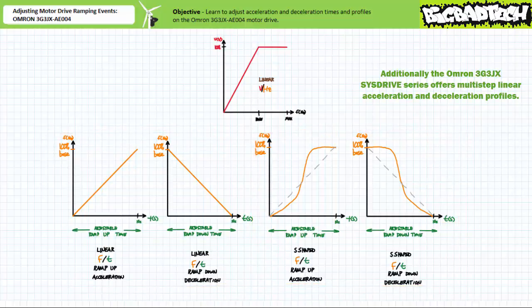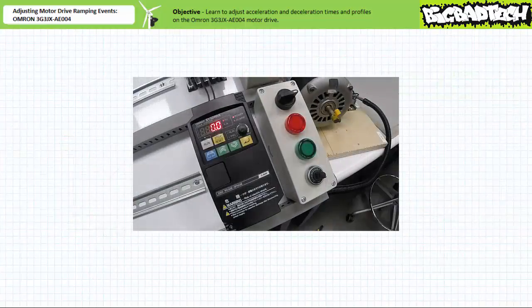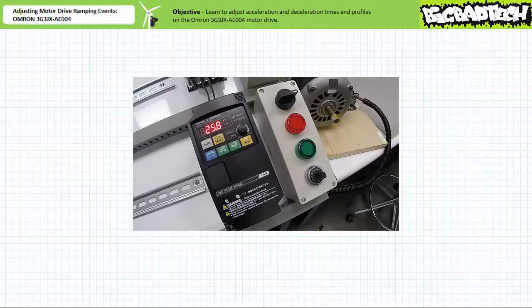The default profile for both acceleration and deceleration is linear with a default value of 10 seconds. For an unloaded motor, this default acceleration and deceleration profile and time is evident, but rather undramatic. When an operator presses run with the external speed potentiometer knob pegged fully clockwise, the motor drive linearly increases applied frequency to 60 Hz over 10 seconds. When an operator presses stop, the motor drive linearly decreases applied frequency to 0 Hz over 10 seconds. The motor decelerates and turns off — evident but undramatic.